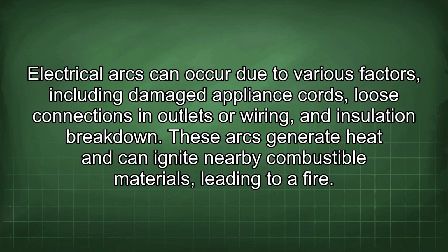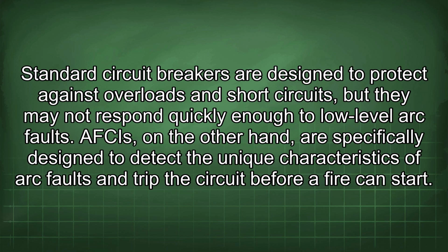Electrical arcs can occur due to various factors, including damaged appliance cords, loose connections in outlets or wiring, and insulation breakdown. These arcs generate heat and can ignite nearby combustible materials, leading to a fire. Standard circuit breakers are designed to protect against overloads and short circuits, but they may not respond quickly enough to low-level arc faults. AFCIs, on the other hand, are specifically designed to detect the unique characteristics of arc faults and trip the circuit before a fire can start.